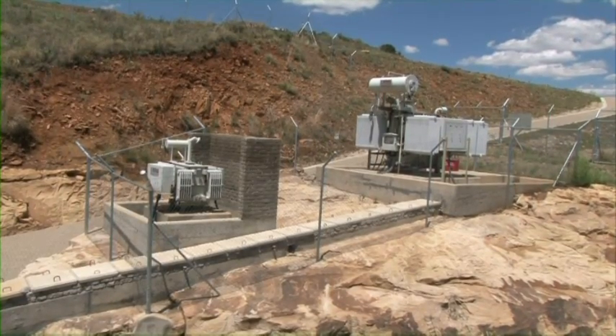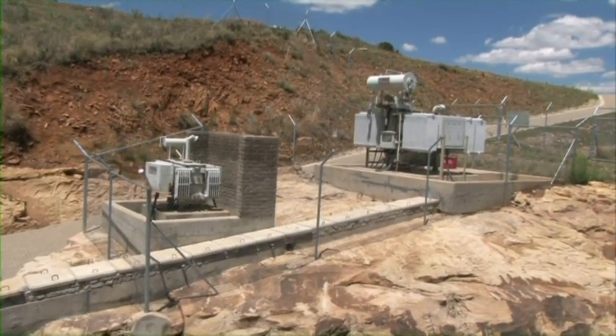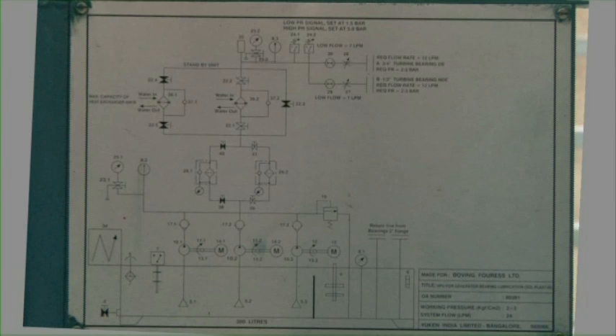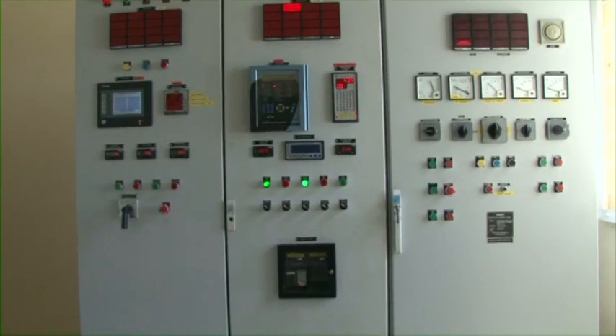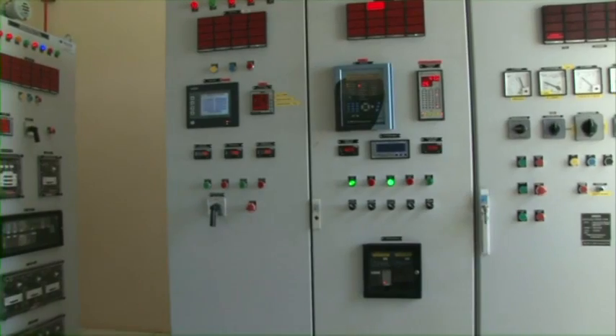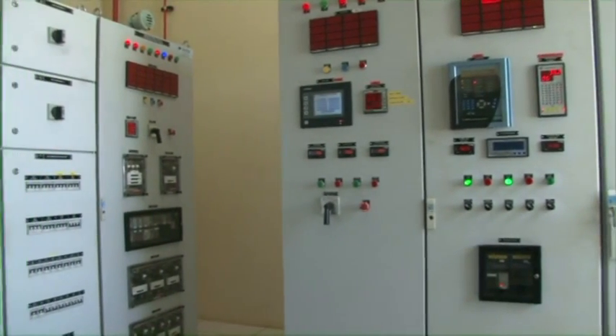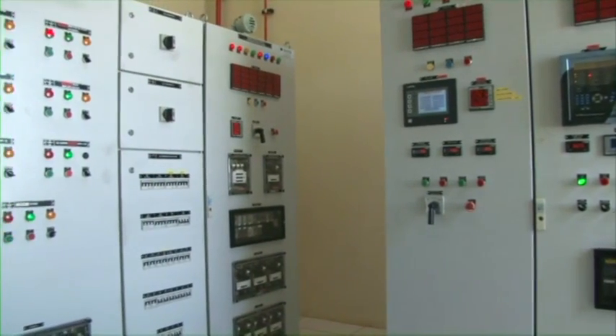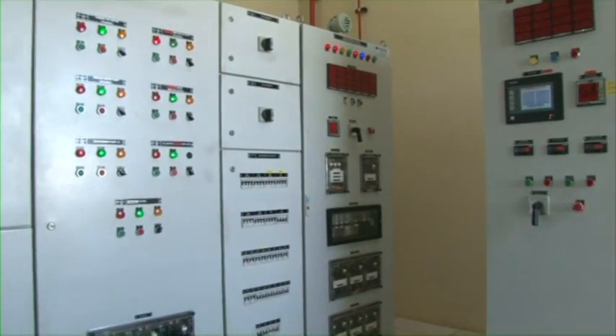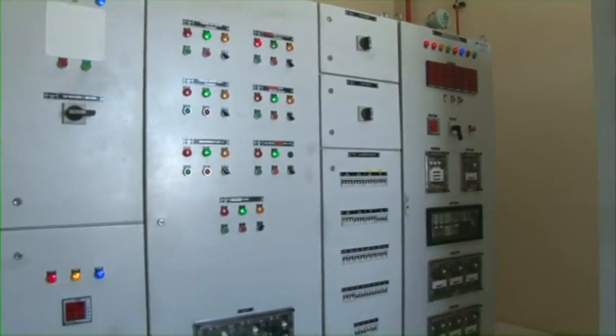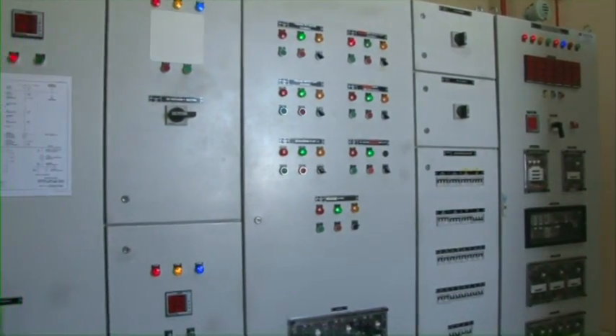After the control system has synchronized our generator with the Eskom overhead line, the generator circuit breaker will close. We call this a switchgear. This switchgear type is a SF6 type gas switchgear, and it's of ABB make. The control system at the power station collects information from the machine room. This includes the auxiliary components, the turbine, the generator, step-up transformers, and consolidates them within the PLC.